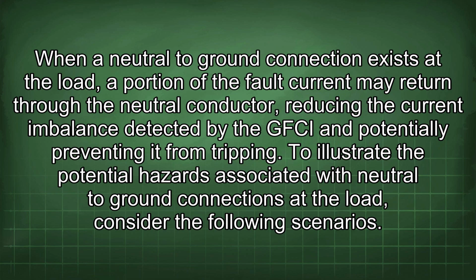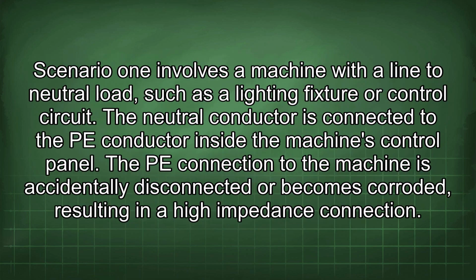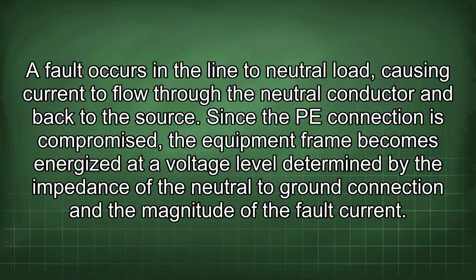To illustrate the potential hazards associated with neutral to ground connections at the load, consider the following scenarios. Scenario 1 involves a machine with a line to neutral load, such as a lighting fixture or control circuit. The neutral conductor is connected to the PE conductor inside the machine's control panel. The PE connection to the machine is accidentally disconnected or becomes corroded, resulting in a high impedance connection. A fault occurs in the line to neutral load, causing current to flow through the neutral conductor and back to the source. Since the PE connection is compromised, the equipment frame becomes energized at a voltage level determined by the impedance of the neutral to ground connection and the magnitude of the fault current.